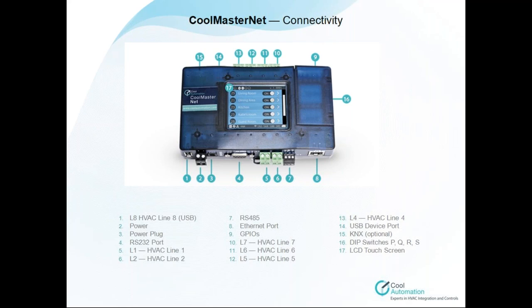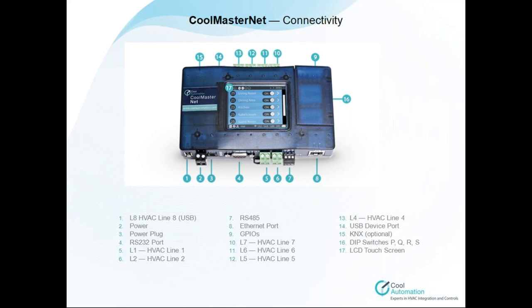Number four and number seven are responsible for home automation systems. In case you have RS-232 or RS-485, either one of them, they must be connected to these terminals. Number five, six, ten, eleven, twelve, and thirteen, all of the lines are responsible for the HVAC systems. Number eight, it's an RJ45 Ethernet connection. In case you have Modbus IP or any kind of net and you want to connect to CoolMasterNet, iRidium, one of the ways to connect is by RJ45.